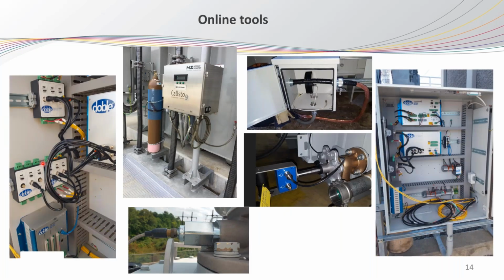For the PD sensors, we have a number of sensors like the UHF drain valve probe. It's a sensor that can detect the PD that can happen inside the transformer. You just put it through the drain valve of the oil. And we have a split core high frequency CT, or HFCT. We can put it around the neutral to detect the PD that can go through the ground, and also the many high frequency CTs, and these are used to detect the partial discharge that happens at the bushing. So we can see here the sensor that is measuring the leakage current and the cable, and this cable is connected to these high frequency CTs to detect any PD spike in the leakage current.